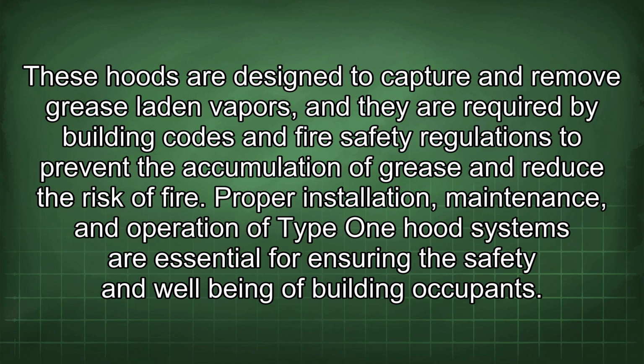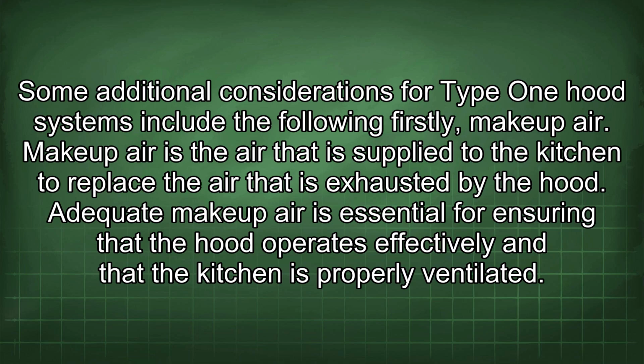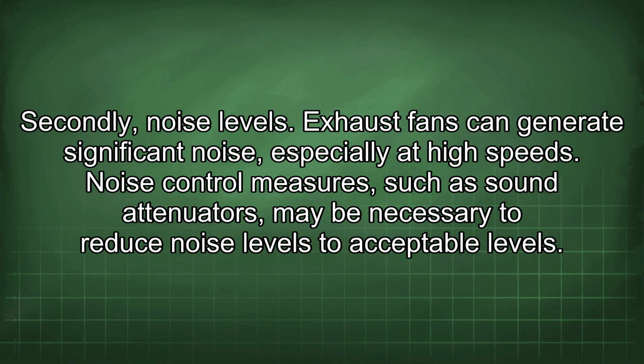Proper installation, maintenance, and operation of Type 1 hood systems are essential for ensuring the safety and well-being of building occupants. Some additional considerations for Type 1 hood systems include the following. Firstly, makeup air. Makeup air is the air that is supplied to the kitchen to replace the air that is exhausted by the hood. Adequate makeup air is essential for ensuring that the hood operates effectively and that the kitchen is properly ventilated. Secondly, noise levels.